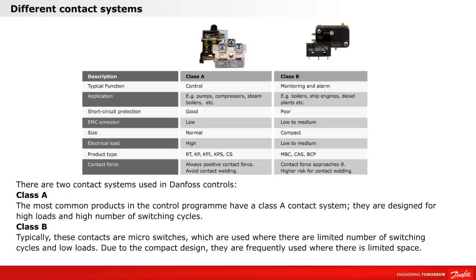There are two contact systems used in Danfoss controls: Class A and Class B. The most common products in the control program have a Class A contact system. They are designed for high loads and a high number of switching cycles. Typically, the Class B contacts are micro-switches, which are used when there is a limited number of switching cycles and low loads. Due to the compact design, they are frequently used where there is limited space.